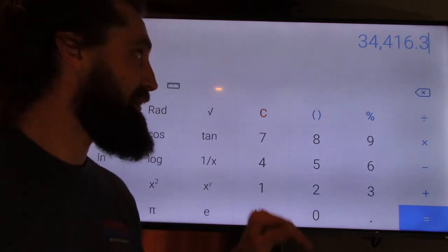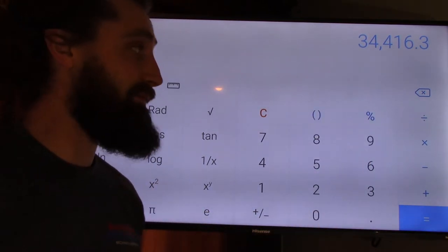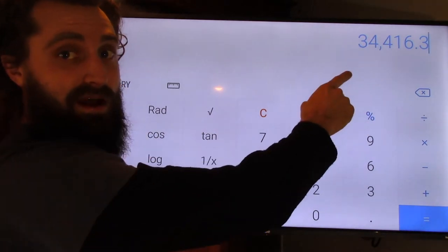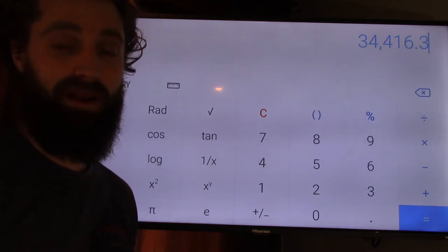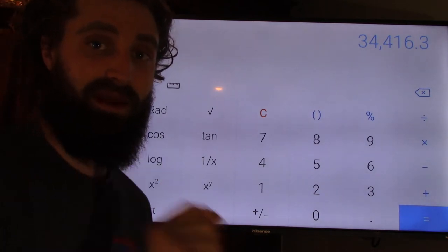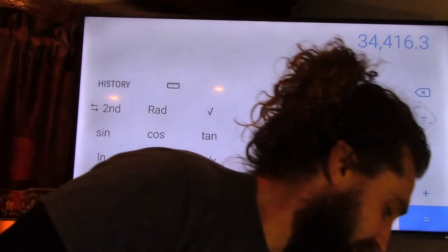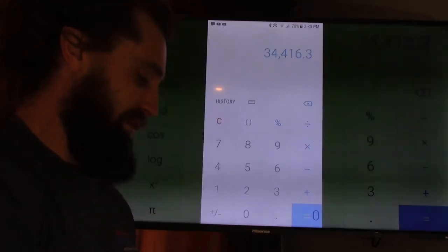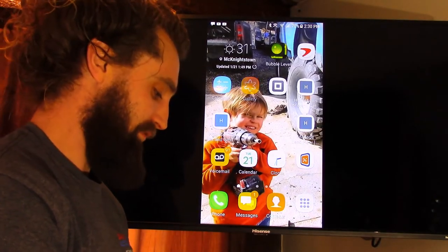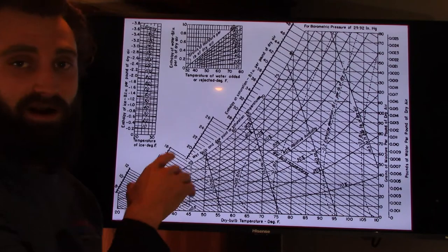Likewise with air conditioners. Air conditioners might be rated at 80 degrees, I'd have to look. But if at 93 degrees outside it's producing 34,000, I'm happy with that. I guarantee if it's doing that at 93, at 80 degrees it's probably producing in excess of 36,000 BTU. So that's really, in a nutshell, going through these things and figuring out capacities of systems.